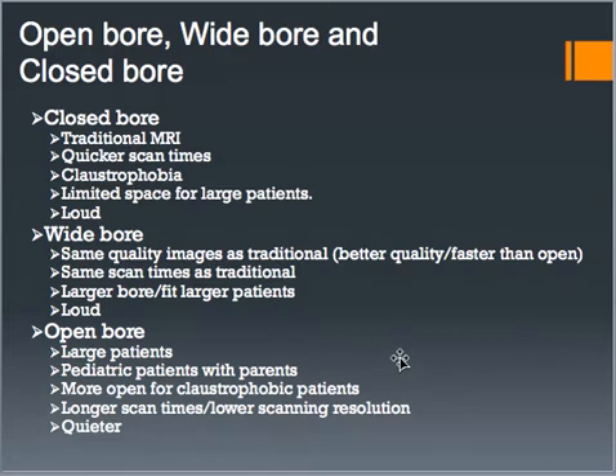But the problem with the open bore scanners was they started to sacrifice image quality. So then manufacturers started producing these wide bore scanners. These scanners have about a 27.6-inch bore or opening. So it opened up just a little bit more. There's a slight image quality loss between closed and wide bore scanners, but it's still much better quality than the open bore, because open bore scanners actually have a weaker magnet. Just for a little bit of reference, an open scanner uses about 0.3 Tesla to 0.7 Tesla, and a closed bore uses about 1.5 Tesla to about 3.0 Tesla. The high magnet strength can improve the image quality due to the increased signal strength. So the higher the Tesla, the better your image quality is going to be.